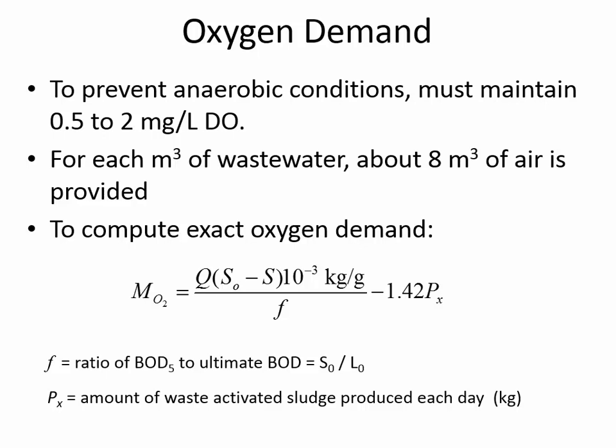Because remember the way we measure their food? We measure their food in terms of oxygen demand. BOD, biochemical oxygen demand. And so if we're measuring how much they ate in terms of oxygen, it becomes very easy for us to calculate the oxygen they require. Here's the conversion factor between grams and kilograms, and we can express these concentrations in terms of grams per cubic meter. Grams per cubic meter is the same as milligrams per liter.